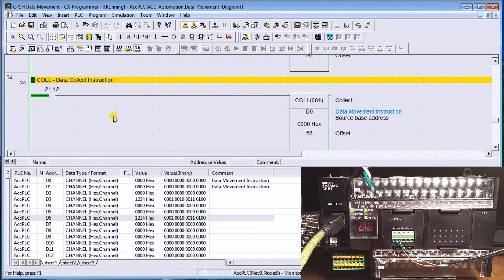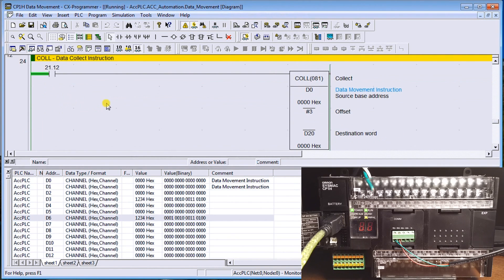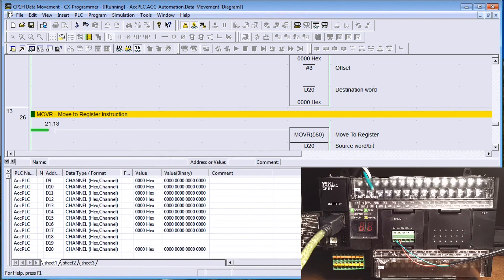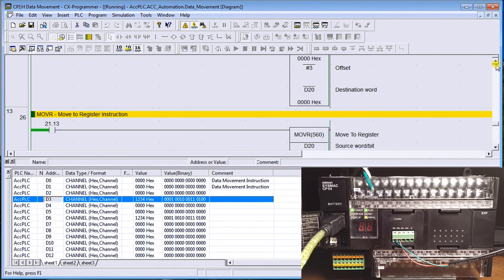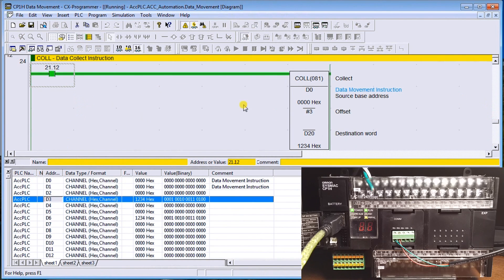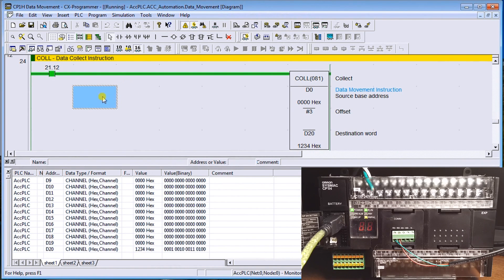Next is Collect Data, which is similar to Single Word Distribute but works in reverse — it takes the base address plus an offset and stores the result in a destination. Base D0 plus offset three gives data memory three, and we store that into data memory twenty. Turning it on, data memory twenty now contains 1234, confirmed both in the live view and in the monitored data memory display.